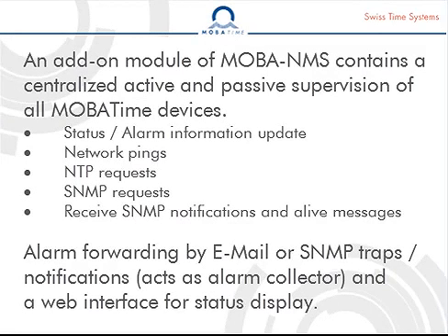An add-on module of MOBA-NMS contains a centralized active and passive supervision of all MOBATIME devices, status and/or alarm information update, network pings, NTP requests, SNMP requests, receive SNMP notifications and alive messages. Alarm forwarding by email or SNMP traps and/or notifications, acts as alarm collector, and a web interface for status display.